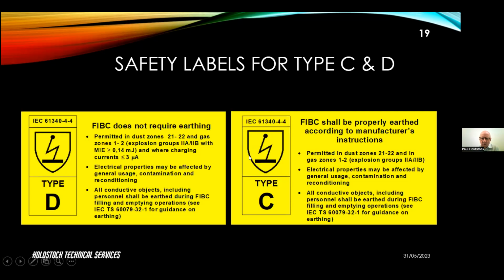But the other thing that's common with both the Type C and the Type D labels is this statement: all conductive objects, including personnel, shall be earthed during FIBC filling and emptying operations. And then it refers to the IEC 60079-32-1 for further guidance. Now, those familiar with bags will say this is very obviously the case with Type D, because it relies on corona, and corona is driven by the field from the charge in the bag itself. As the charge is dissipated, the field will fall to a point where corona no longer occurs.